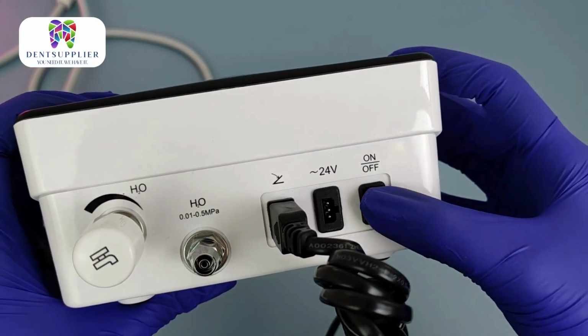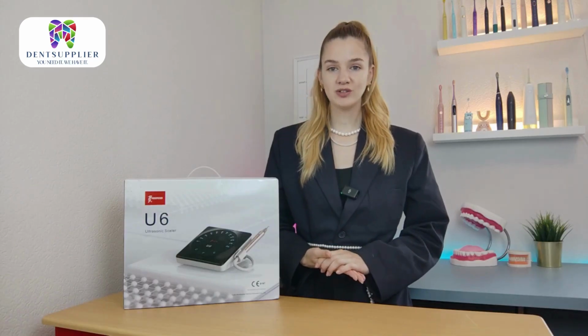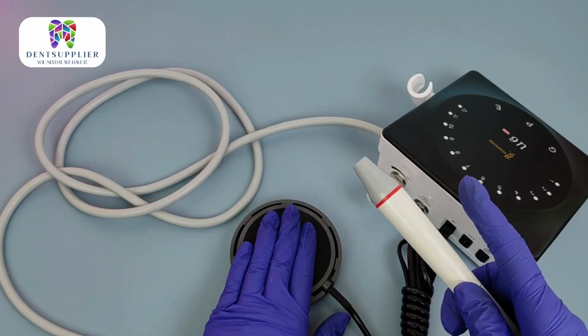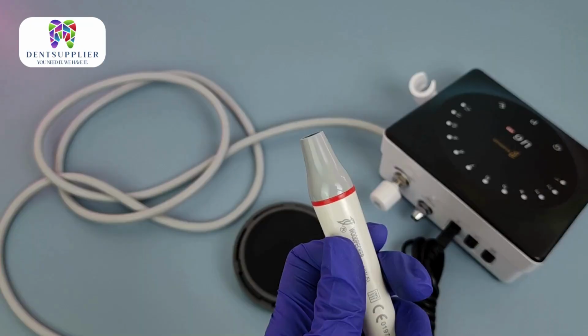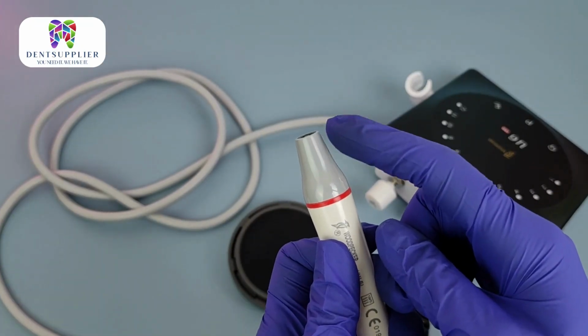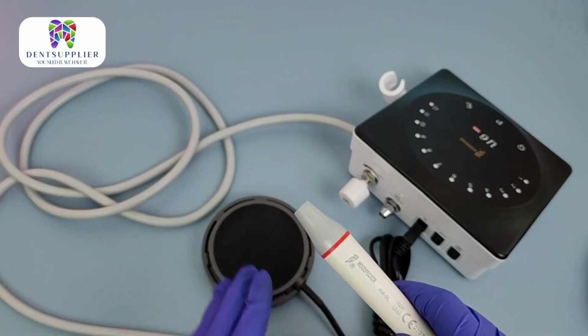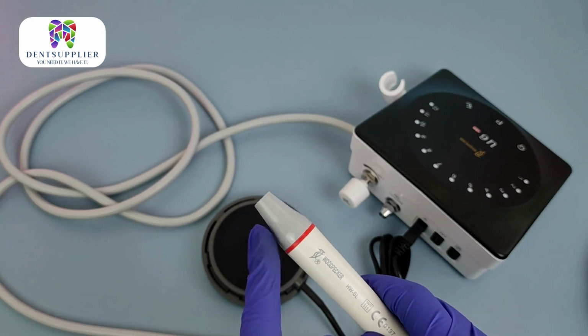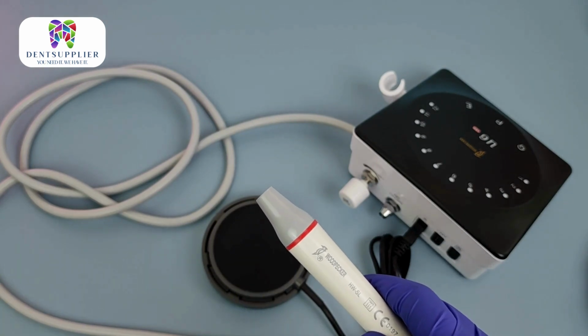Turn on the power switch. Under normal working condition, the frequency of the tips is very high. Step on the foot switch and the tip will start to vibrate, and the LED lamp on the top of the handpiece will light as well. If you release the foot switch, the LED lamp will keep the light for 10 seconds. After finishing operation, keep the machine working for 30 seconds with the water supply to clean the handpiece and the tip.